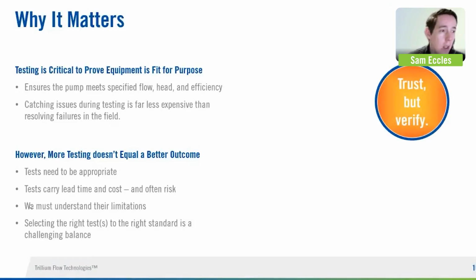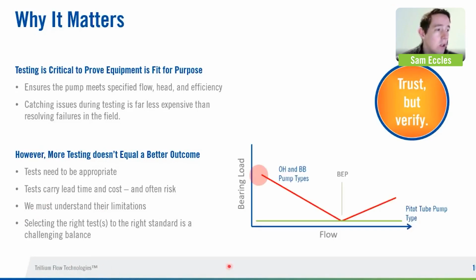So if we look on the next chart, what this is trying to show in red, I'll not spend too much time. So this is increasing flow and increasing bearing load. So all it's showing is as we move the flow back away from BEP, where the load is at the lowest, and we come towards a zero flow, or what we'll typically call closed valve, this is where the pump has no flow, and all the energy from the motor is going straight into heating the fluid. What comes with that is a drastic increase in bearing load.